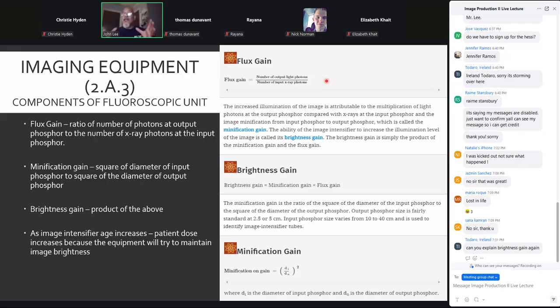The only variable phosphor in an image intensifier is the input phosphor, and it's always going to be bigger than 5. So again, a number greater than 1 for the minification gain. Now, once you solve flux gain and minification gain, take those two numbers, multiply them together, and that gives you the brightness gain.